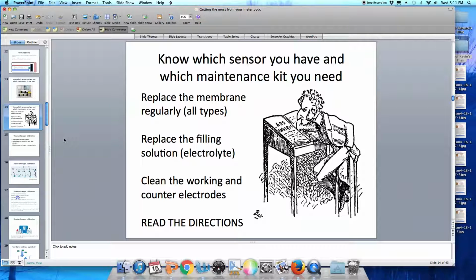It is very important to know what kind of sensor you have and what maintenance kit you need. You're going to frequently have to replace the membrane, and this is true of all types of sensors. This is true for polarographic, galvanic, and luminescent sensors because the membranes can become clogged. For the electrochemical sensors, you will need to replace the filling solution or the electrolyte. And both the working electrode and the counter electrode can be cleaned, usually with very fine grit sandpaper. Whatever you do, read the directions so that you know how to replace the membrane, replace the filling solution, and clean the various electrodes.